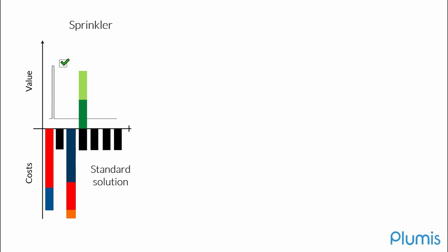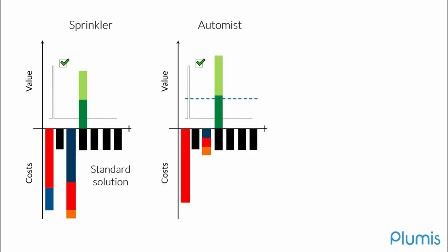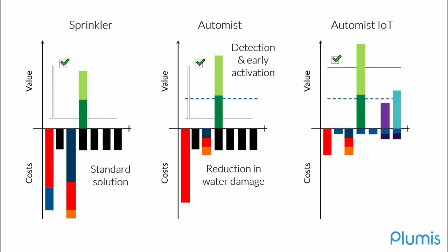Automist can offer a very different value proposition and service to the standard solution you get with a traditional sprinkler system. This is primarily made possible by the fact that, one, we're introducing detection with our system as standard, which means you can operate earlier. And secondly, because we're using significantly less water, we can minimize the amount of water damage that happens in an incident. And for those who would like to try something else different, there is our connected solution that has the same water damage reduction qualities, but can also offer real-time compliance and the opportunity to upgrade to enable a host of new data services over time.